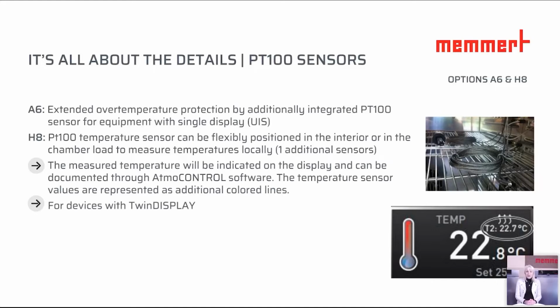This flexible PT100 sensor measures and records the actual temperature. That is then also visible on the controller under, for example, here T2. That means here we have, additionally to the actual temperature, also the actual temperature of the flexible sensor with 22.7. So that is to record and see the temperature, but it's not for controlling the temperature. Also, it will be recorded in the log file and also in the memory, so it's also a storage of the data. This was in regard to a flexible sensor.